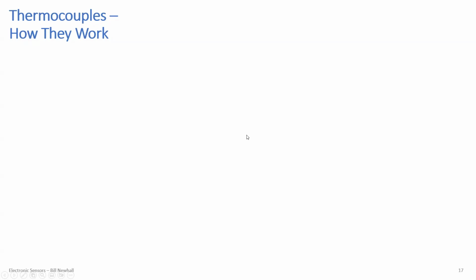Let's move on to thermocouples. You can use semiconductor-based devices, silicon-based devices, and thermistors for measurements from room temperature up to maybe 200 or 300 degrees, depending on the part. But if you need to measure very high temperatures, like exhaust gas or a combustion chamber, above a few hundred degrees, maybe into the 1,000 to 2,000 degree level, then you need to use thermocouples. So it's worth covering how these work, and more importantly, how you use them.